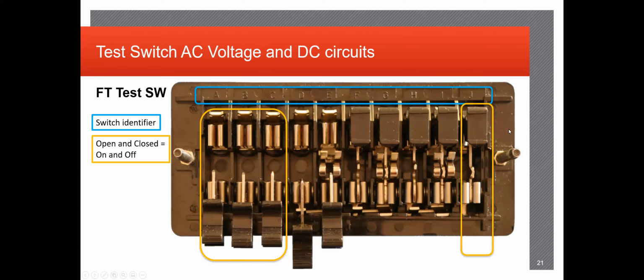Identifying the types of test switches specifically, we're looking at the obvious identifier. In this case, it is Alpha, Bravo, Charlie, ABCD, et cetera, and the obvious open, close. For AC circuits specifically, it would be more or less common to see your A, B, and C phase voltages coming in to their correlating test switch, not necessarily ABC itself, but at least all ganged together in the same block, and maybe your neutral on the other side. It just depends on the client specifically and how they usually come up with their standards.